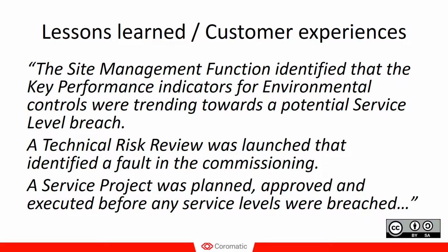So here's a customer experience where the site management function identified that the key performance indicators for the environmental controls were trending towards a potential service level breach. Had these temperatures and humidity levels continued in the direction they were trending, there would be an SLA breach in the future. So the site management function launched a technical risk review of the environmental controls to see what the problem was.